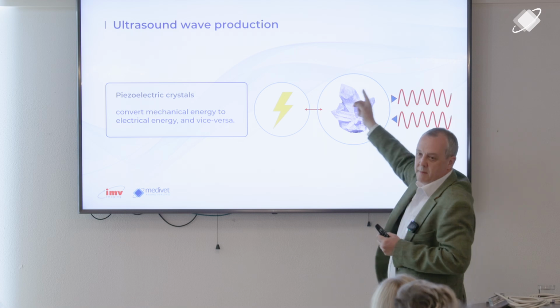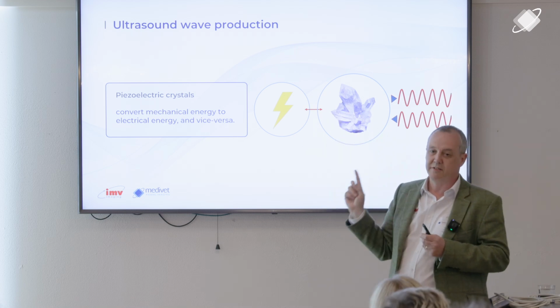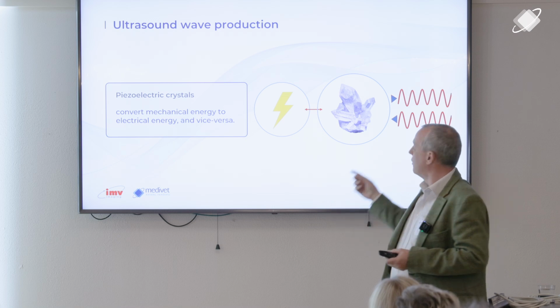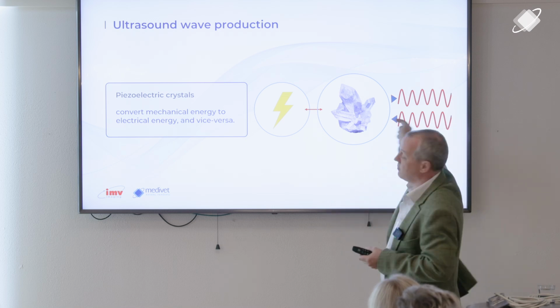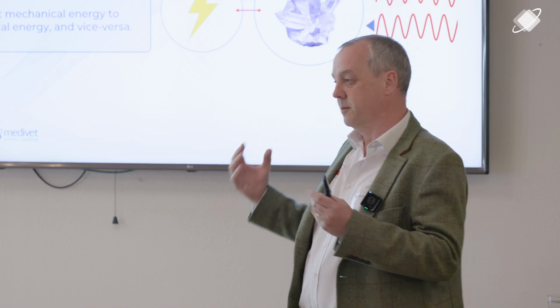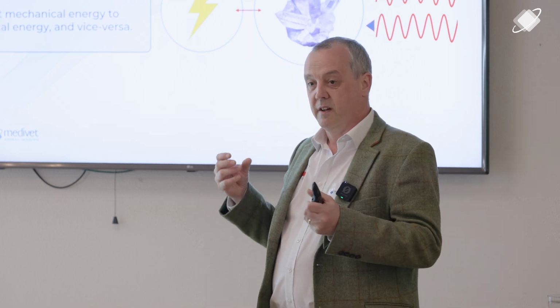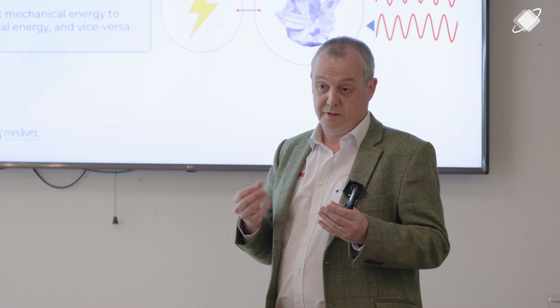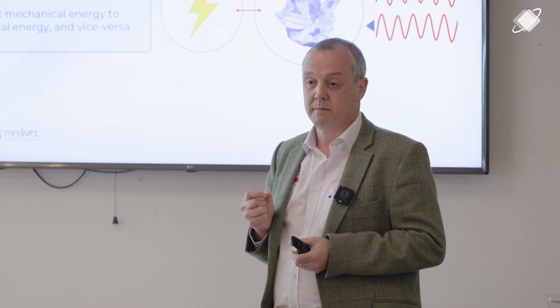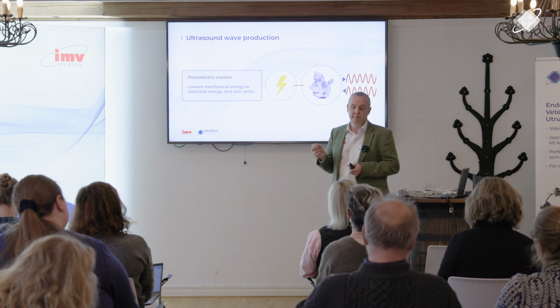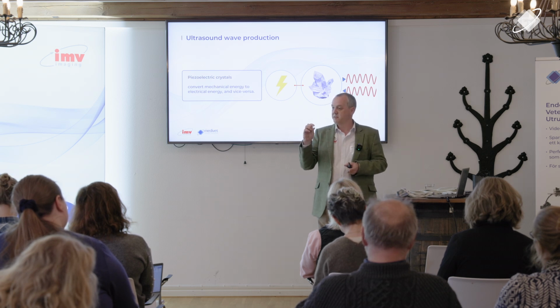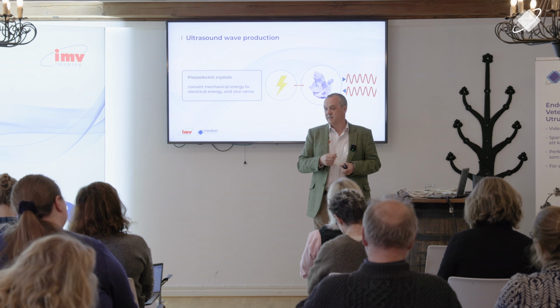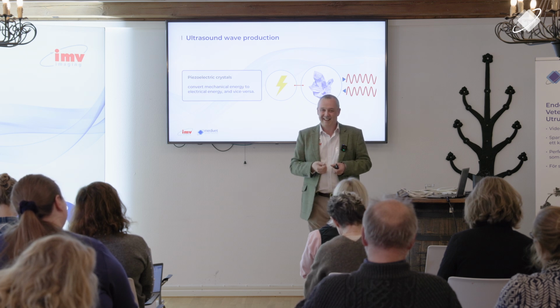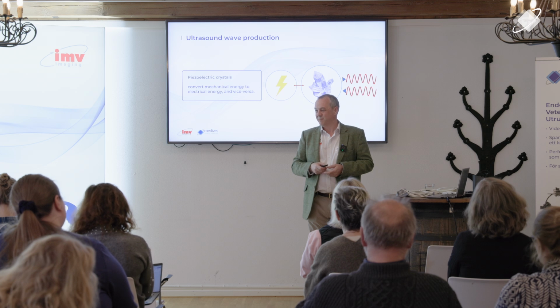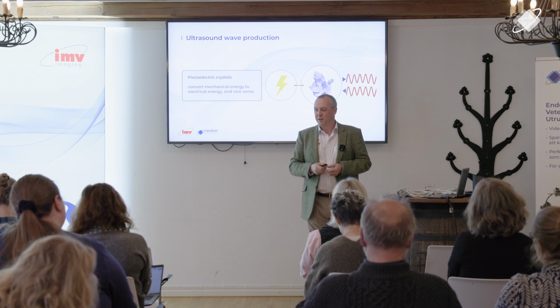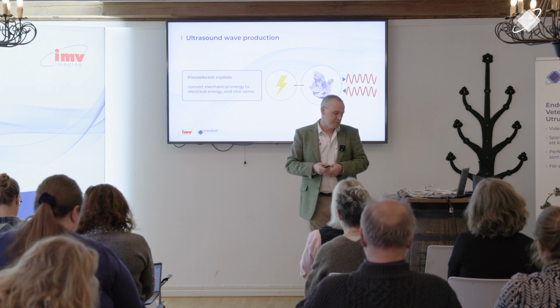When those ultrasounds encounter tissues of differing densities or acoustic impedance, a reflection happens. And when that reflection comes back, it hits the crystal, and it's a reverse process. The crystal is deformed by the ultrasound and produces a voltage. And all the ultrasound machine is doing is measuring that voltage and assigning a shade of grey to it. Now, I've greatly simplified that, and some of my physics buddies back in Scotland will go into a lot more depth on that, but you don't really need much more.